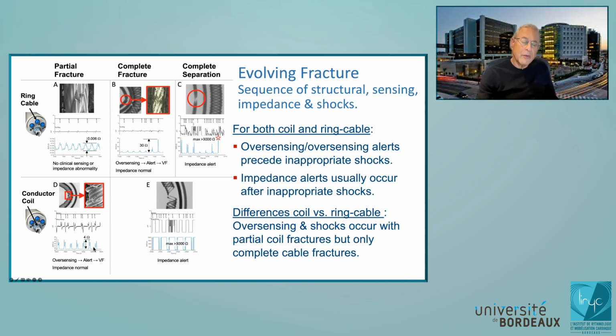Now there is a difference between the way coils and cables break. Let's start with the cable, it's on top—you can see we can break several filars. These things are super hard to see, and even with high resolution radiographs and photomicrographs we couldn't see them well. So to be 100% sure we took them off and did scanning EM, electron micrographs, and you can see here we got several broken filars, and the actual change between peak and trough impedance here is 0.006 of an ohm. That's because these other conductors are so good they barely notice that these filars are missing.